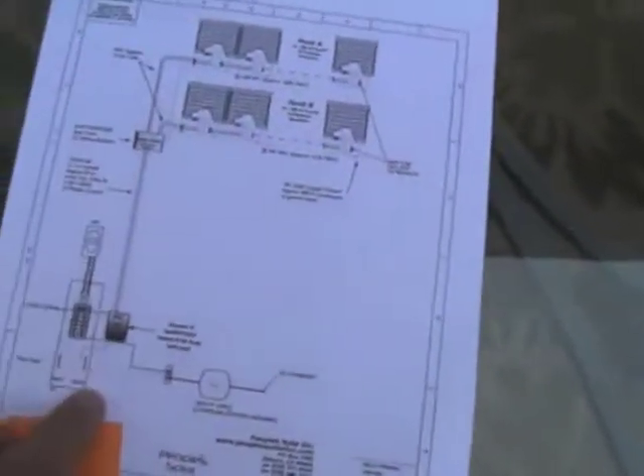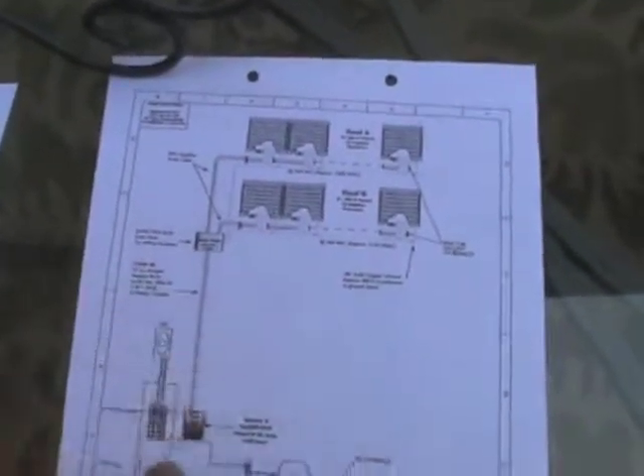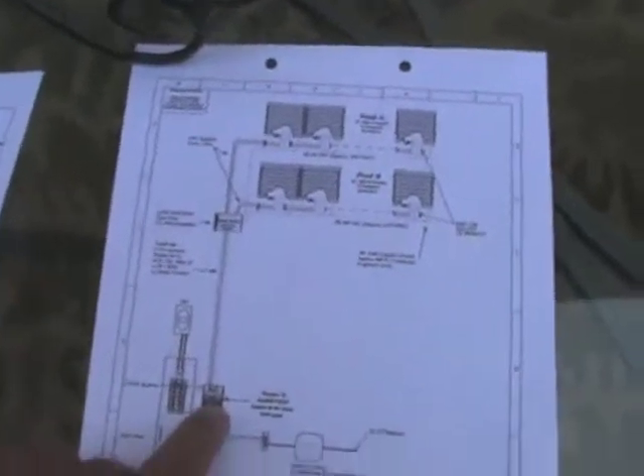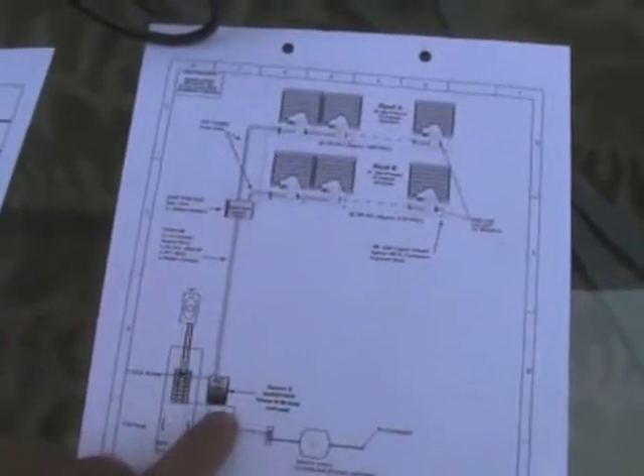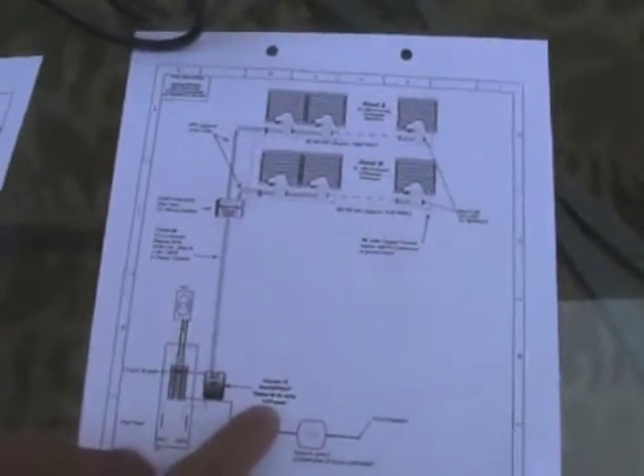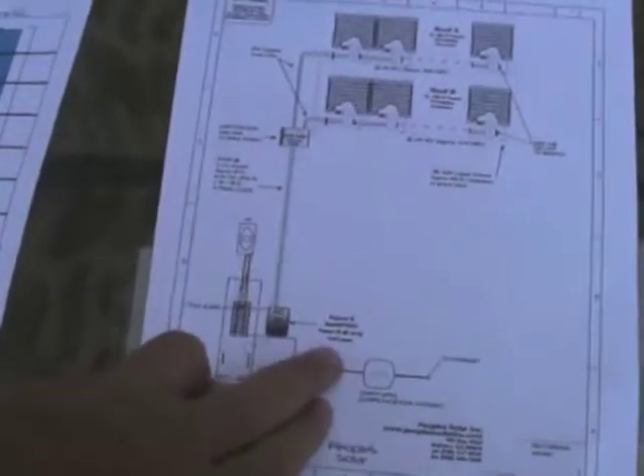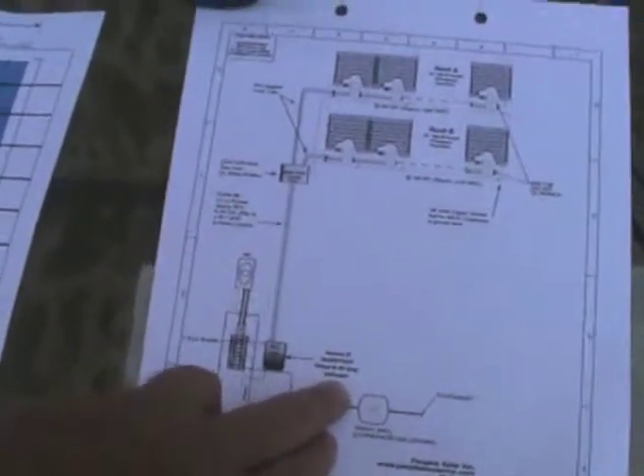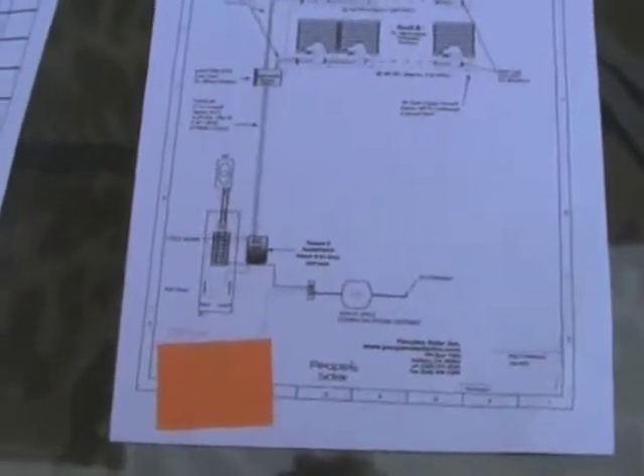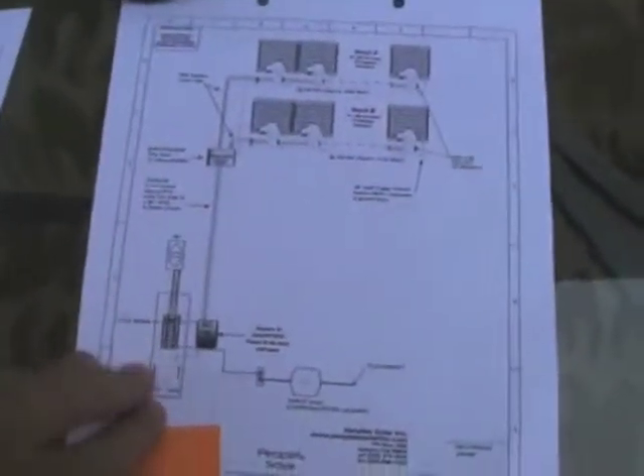So all of your electrical diagrams are done. Everything you need. We even approximate how many feet of wire, in this case number 8 wire, you need to purchase. The disconnect, what type of disconnect you want to use. We recommend a 60 amp, 600 volt VAC system. Square D makes excellent disconnects. And also you can use fused or unfused. I've seen consumers use both. But the point is your system is safe, it's fire safe.